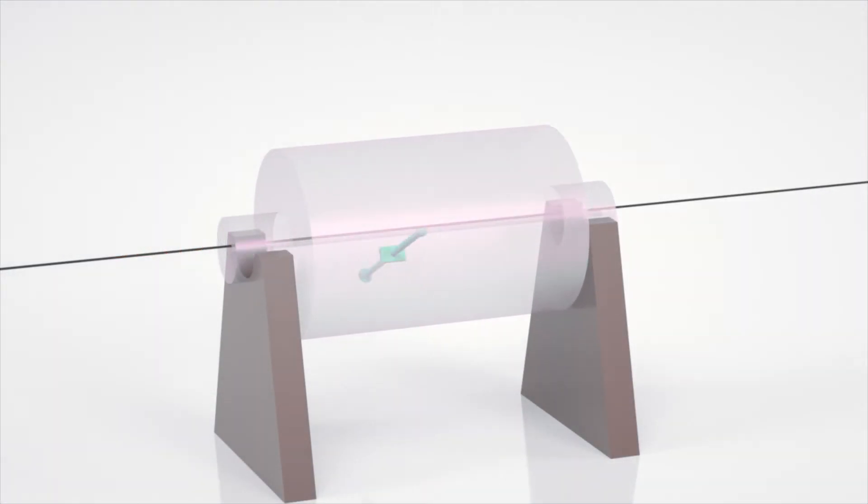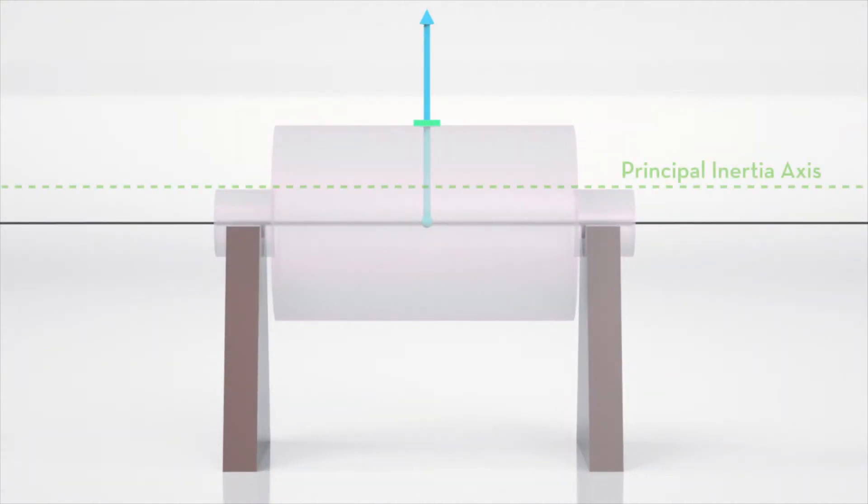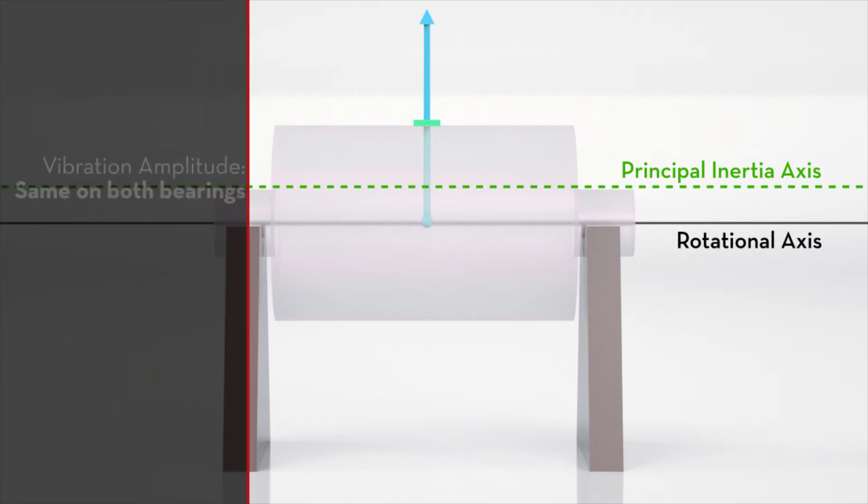Static unbalance occurs when the imbalance is at the center of gravity. The principal inertia axis is displaced from the rotational axis. The two axes are parallel. The vibration amplitude will be the same on both bearings. The phase angles will be the same.